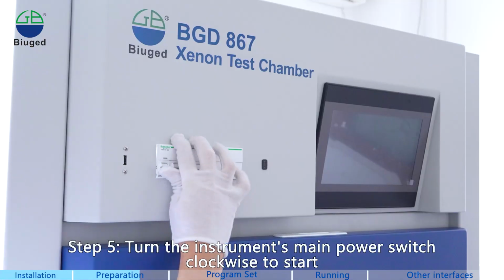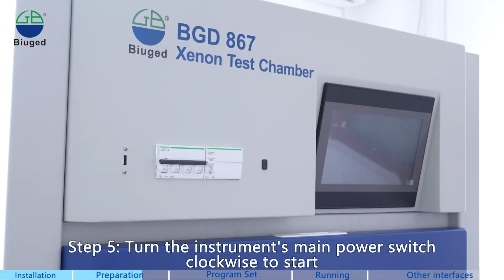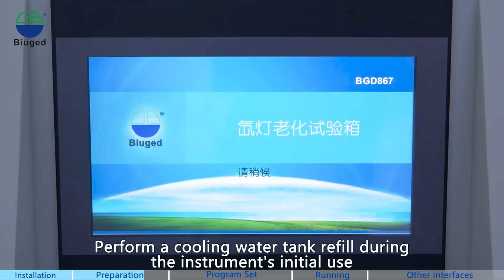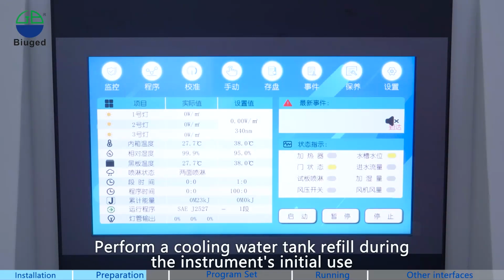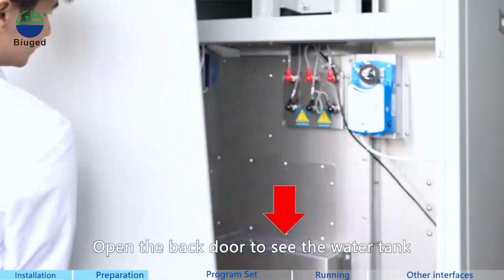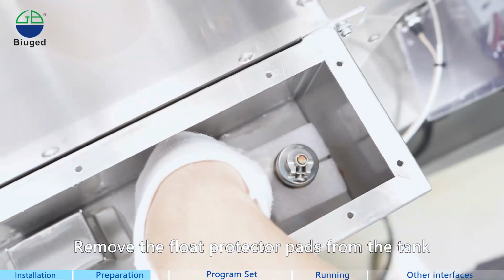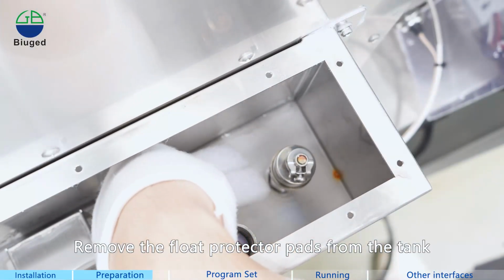Step 5. Turn the instrument's main power switch clockwise to start. Perform a cooling water tank refill during the instrument's initial use. Open the back door to see the water tank. Remove the float protector pads from the tank.